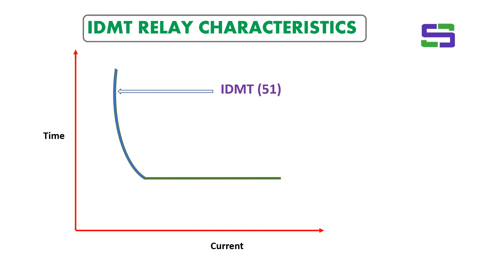The 51 relay has basically two parts. One is the inverse characteristic up to a certain point. The 51 relay is used for overcurrent protection in electrical power system networks. It is plotted on the TCC curve — the time current characteristic curve — where current is on the X axis and time is on the Y axis.